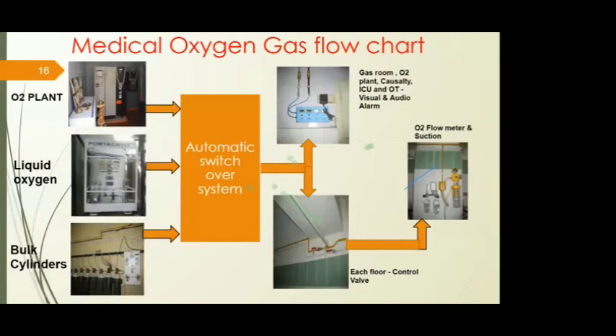They will have the O2 plant, which has the capacity of 30 to 40 cylinders, and they will have the liquid oxygen tank. If they have the liquid oxygen tank, it has to be licensed - for the tank as well as the installation, it has to be licensed from PESO. And the third source will be the bulk cylinder, which is the D-type cylinders.